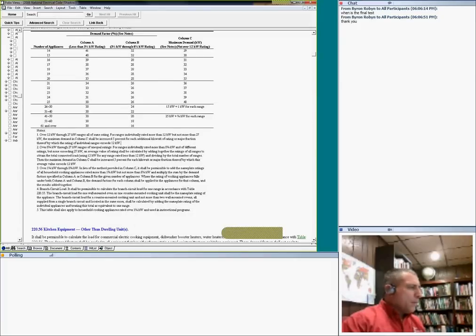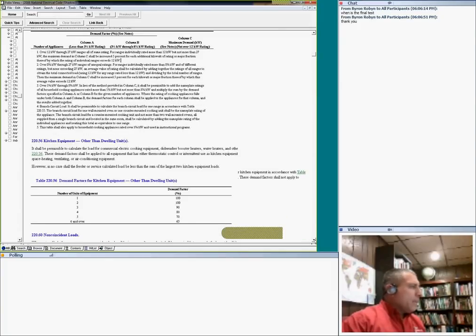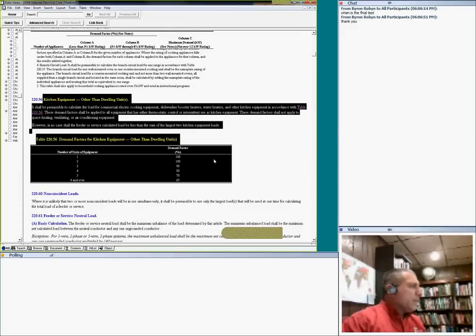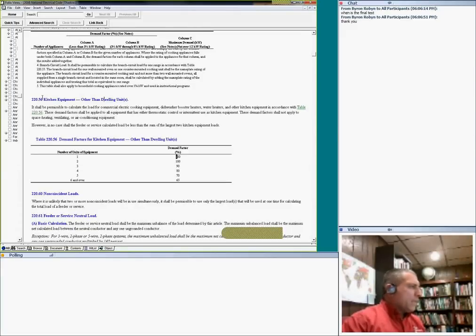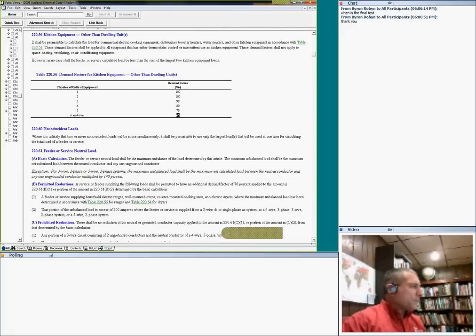Just a quick review of that table. Kitchen other than dwelling, you apply this. If it's a kitchen, McDonald's for example, you add all the cooking equipment and you multiply it by a demand factor. If you have 12 of them, you cut them by 65%. That's not residential.